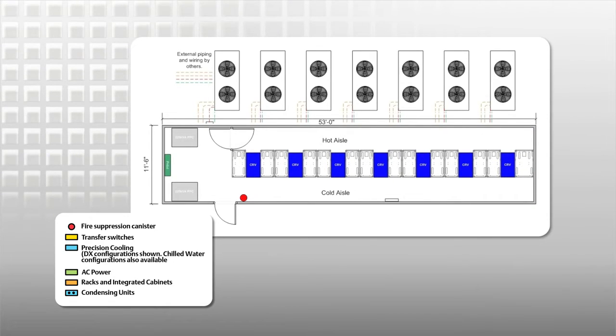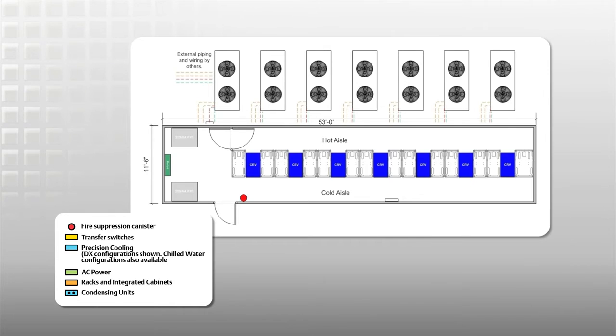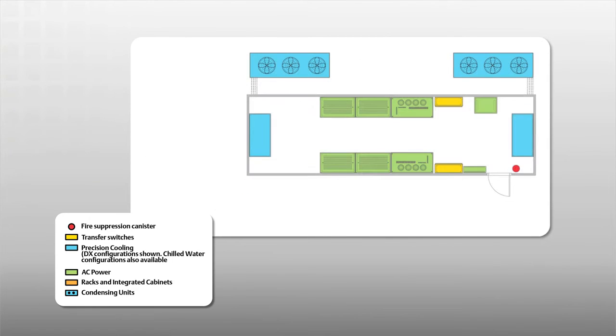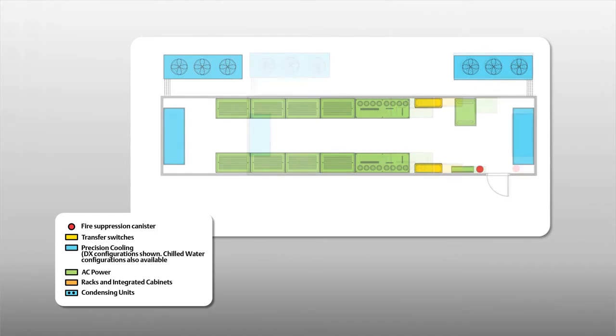The IT enclosure has 14 racks supporting 200 kW of capacity with 2N power redundancy and N+1 cooling redundancy. There are two separate sizes of power enclosures, available in 200 kW and 400 kW capacities in either N or 2N power configurations. All power enclosures have 2N cooling redundancy.